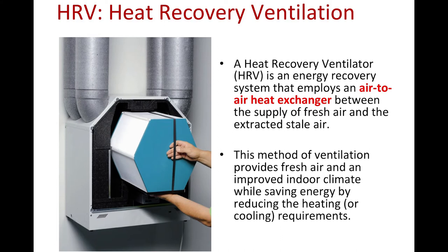How to do that? What's called a heat recovery ventilation system. The magic of a heat recovery system is that, as I said earlier, you're bringing in fresh air and exhausting stale air. And where those two air streams pass one another in this thing called a heat recovery core, there's material that divides the airstream up into many, many tiny air streams. Because there's a lot of surface area to volume ratio, there's a lot of heat transfer. It's just the exact same principle when somebody comes in from the cold and you shake their hands. The second law of thermodynamics is happening, and physics just makes energy go from warmer to colder. And that's how an HRV works. So there's no air leakage across those air streams, but there's a thermal energy transfer that happens.